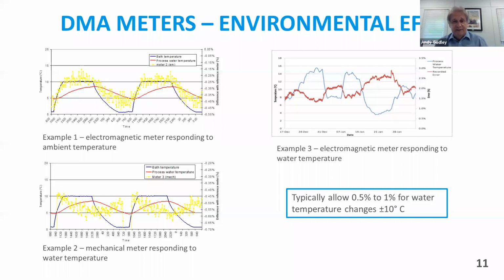So again, this is not necessarily a highly predictable effect. We know that some meters are affected by water temperature, some meters can be affected by ambient temperature. So when we're looking at water balances and looking at meter data, particularly where we're seeing seasonal effects between summer and winter, where you can get changes in water temperature of 10, 20 degrees, we would typically make an allowance of 0.5 to 1% of that to be due to the effect of the water temperature or the ambient temperature on the meter itself, rather than necessarily a leakage effect.